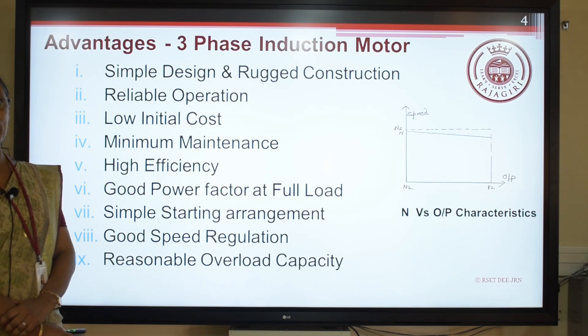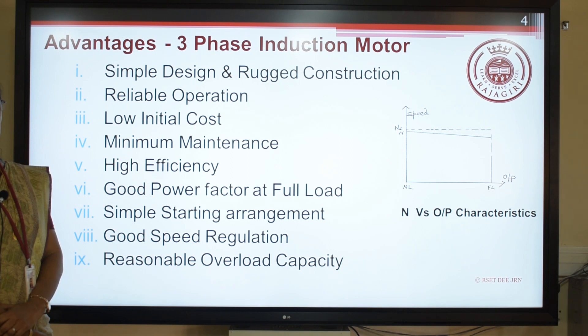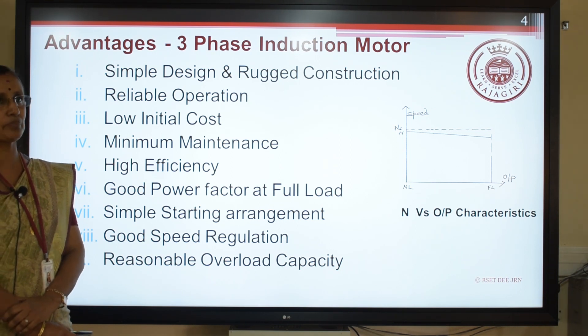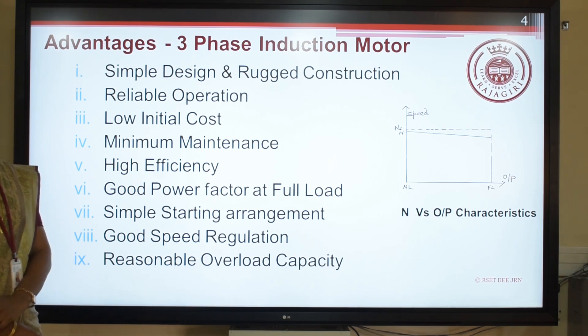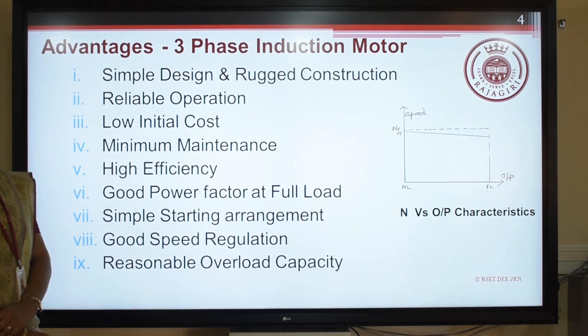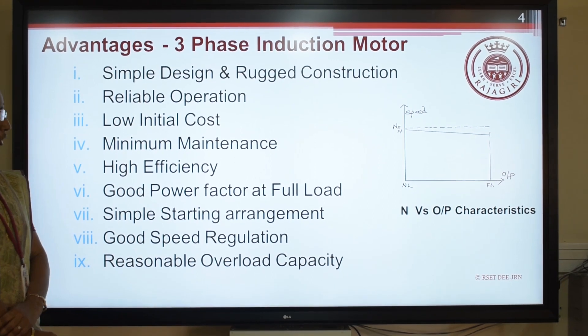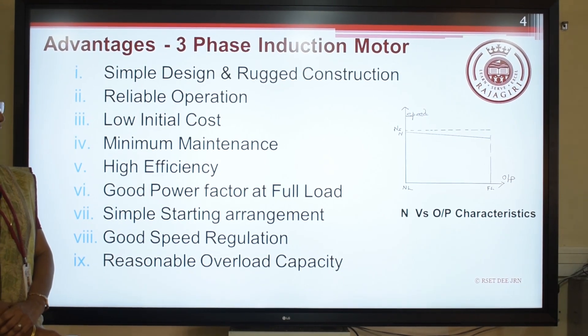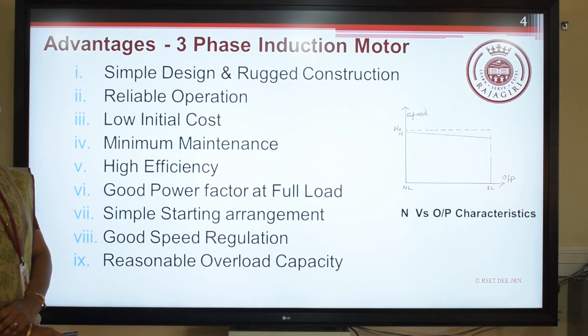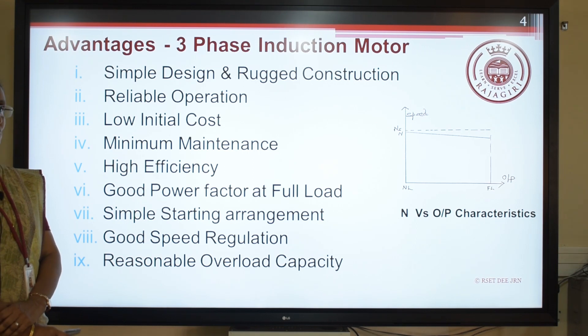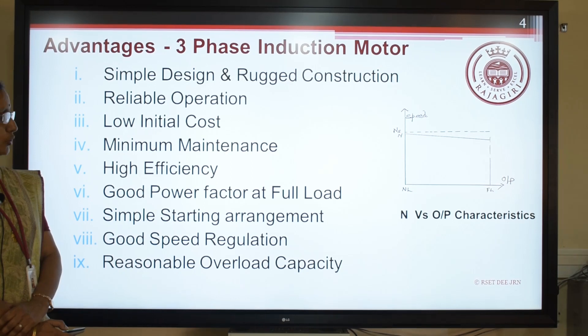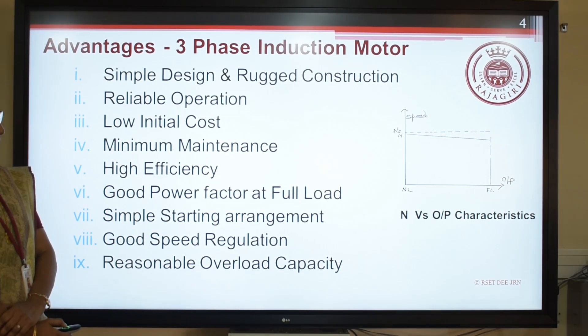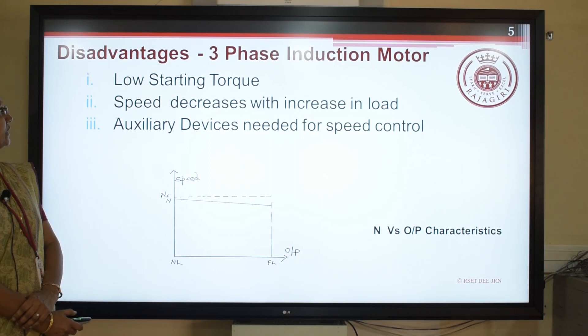Following are the advantages of three-phase induction motor: simple design and rugged construction — it can be used for any harsh environment; reliable operation; low initial cost; minimum maintenance; high efficiency of the order of 85%; good power factor of the order of 0.85 lag; simple starting arrangement to reduce the heavy inrush of current during starting and acceleration; good speed regulation and reasonable overload capacity.